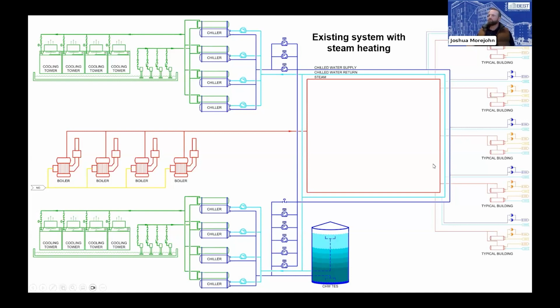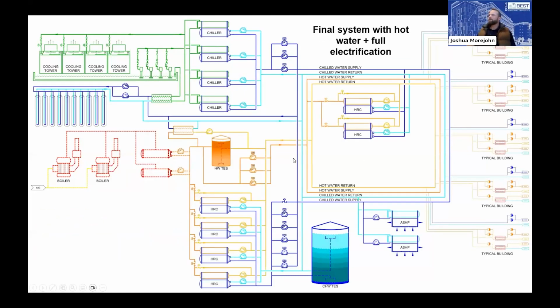Of note, in this previous system, those 2 heating and cooling systems were completely separate. But the new system, this is showing kind of the final state of where we're headed with the heat recovery chillers providing the hot water. Now we're tying our chill water and our cooling and heating systems together, and not having to run the cooling towers as much.